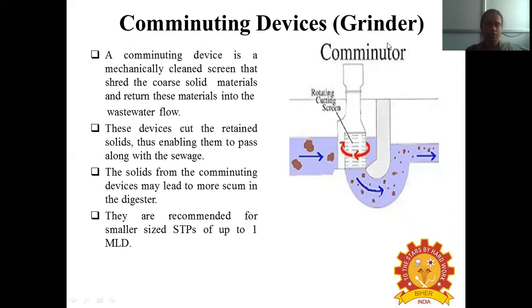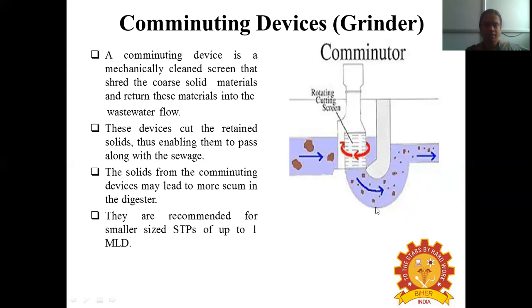A comminuting device is a mechanically cleaned screen that shreds the coarse solid materials and returns these materials into the wastewater flow. These devices cut the retained solids, enabling them to pass along with the sewage. The solids from the comminuting device may lead to more scum in the digester. They are recommended for smaller sized sewage treatment plants of up to 1 million liters per day. The comminutor has a rotating cutting screen that cuts large particles into smaller ones, which then pass to the next treatment stage.